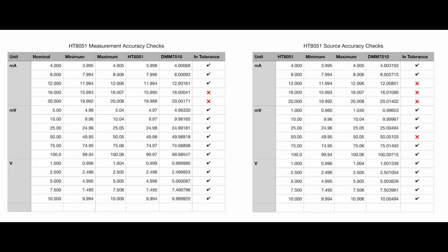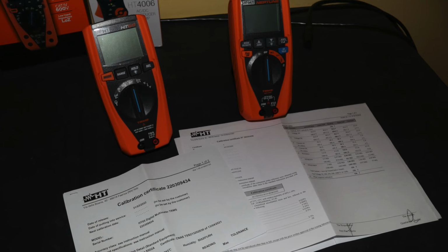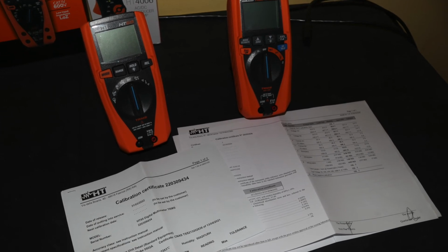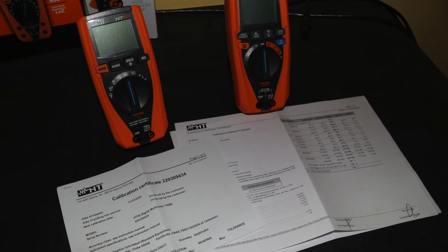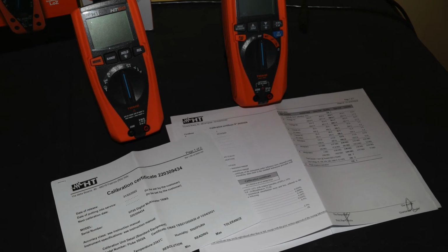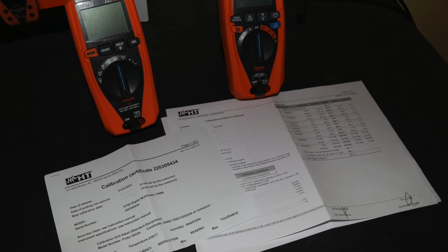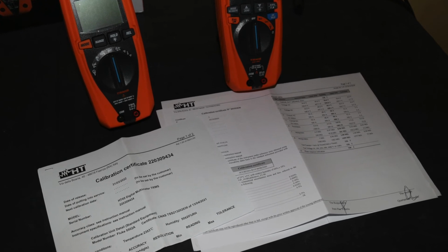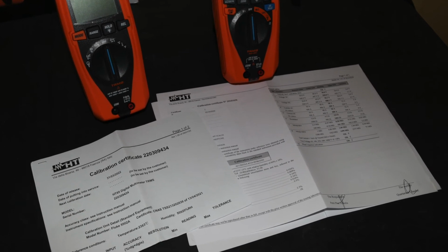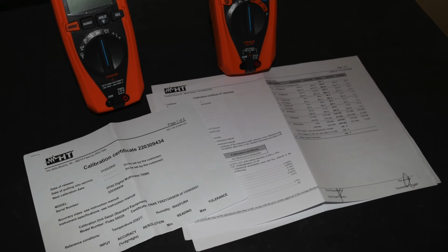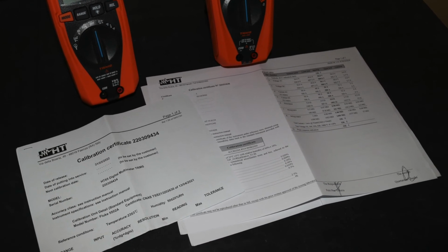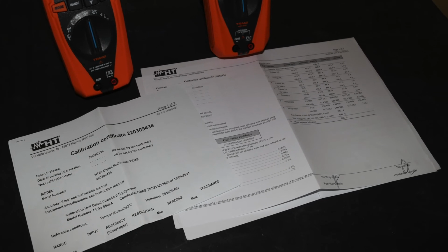I don't have anything to compare this to. Strangely enough, this instrument does not come with a calibration certificate, unlike the two multimeters that I've purchased from them, the HT65 and the Neptune. They both come with manufacturer's calibration certification. The HT8051 doesn't come with one at all, which I find slightly strange, because if there's one instrument I would want to have a calibration on, or I would regard as being more important to have a calibration on, it would be something like this Process Calibrator, as opposed to a standard digital multimeter.